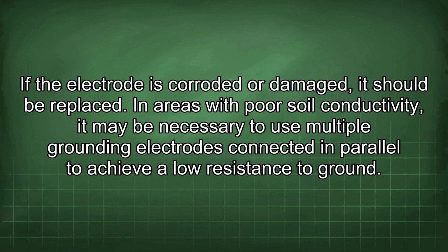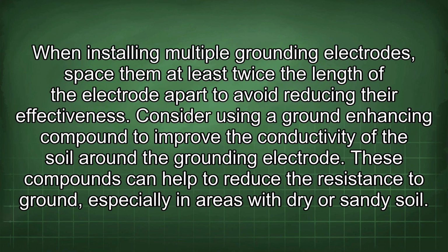In areas with poor soil conductivity, it may be necessary to use multiple grounding electrodes connected in parallel to achieve a low resistance to ground. When installing multiple grounding electrodes, space them at least twice the length of the electrode apart to avoid reducing their effectiveness. Consider using a ground-enhancing compound to improve the conductivity of the soil around the grounding electrode. These compounds can help to reduce the resistance to ground, especially in areas with dry or sandy soil.